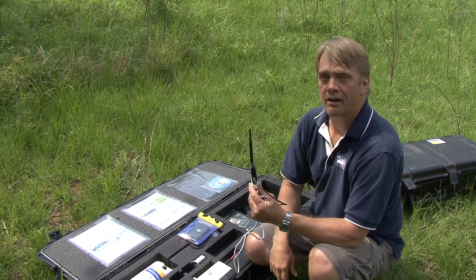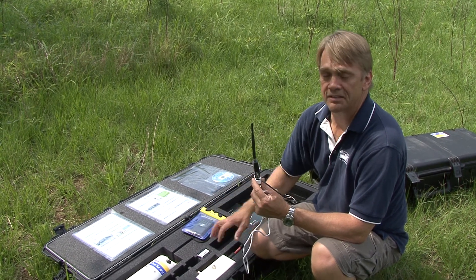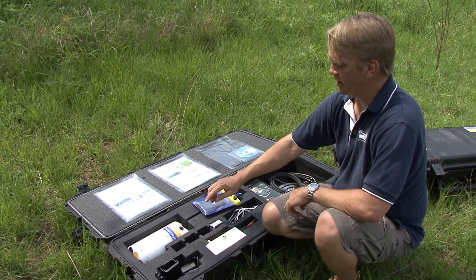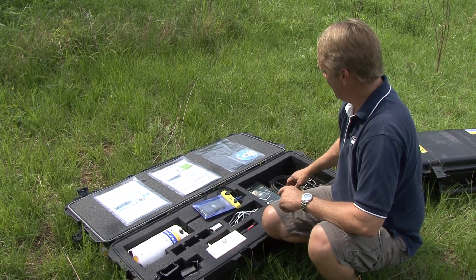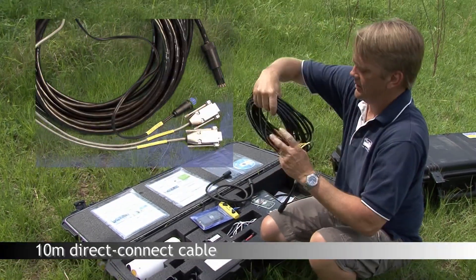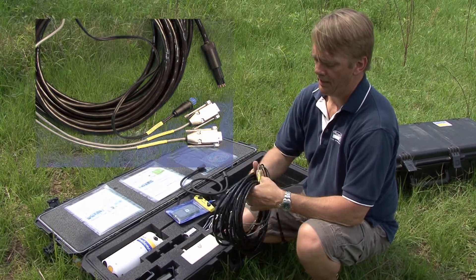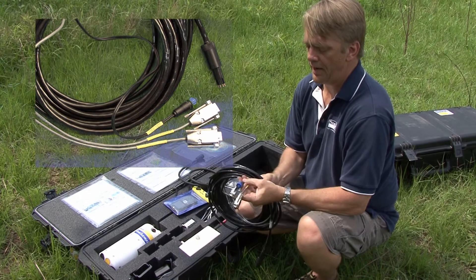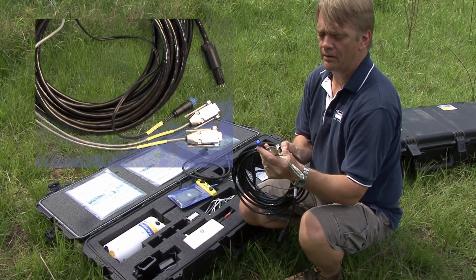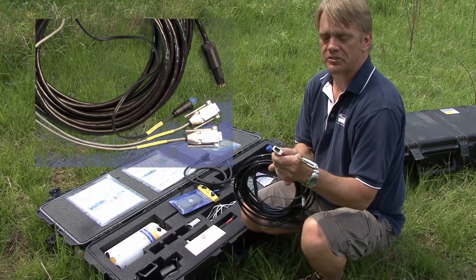This dongle has a range of approximately 200 meters. The phone has a range of approximately 60 meters. If you're not going to use telemetry to communicate with the River Surveyor, it also comes with a 10 meter cable. This plugs directly into the M9, and this is the AC power adapter or power connector. Here's the connector for the GPS if I want to use an external GPS.